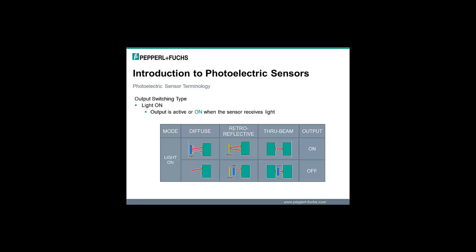These terms apply only to photoelectric sensors. Light-on means the sensor's output is only enabled or on when it receives light; otherwise the output remains off. For diffuse mode sensors, when an object breaks the light beam, the output goes on. For retroreflective and through beam mode sensors, when an object breaks the beam, the output goes off.